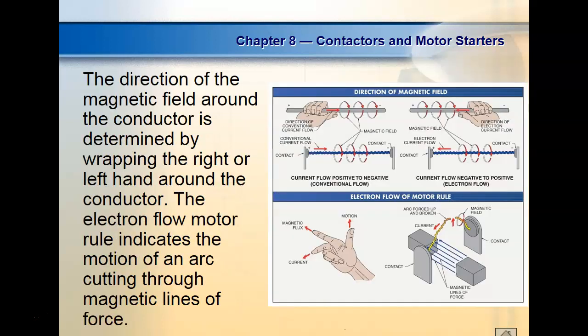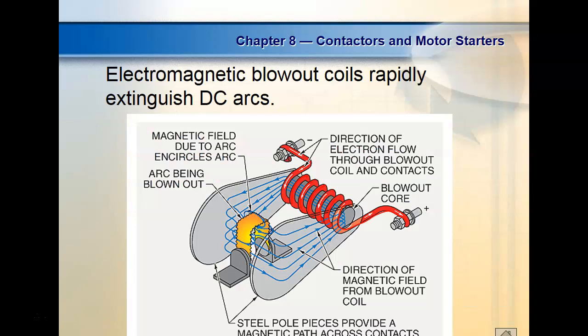So one of the techniques they use in these big old things is what's called a blowout coil. What happens on the blowout coil is the current through the motor runs through the coil, creates a magnetic field, then it comes up here and puts a magnetic field that moves across this thing. Now when the motor breaks, the current through the coil goes to zero, which causes the magnetic field to collapse, which causes this magnetic field to move through the arc. And it literally blows the arc out. We had a crane out here that still ran off DC, and one of the motors wouldn't stop. One of the wipers on the blowout coil had come loose and fell down, so it didn't extinguish the arc. So these are blowout coils.